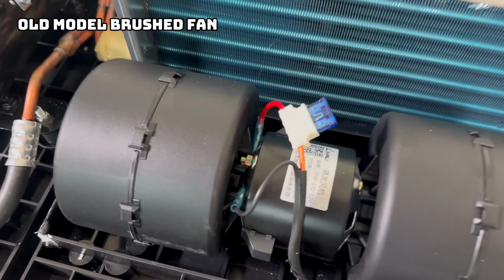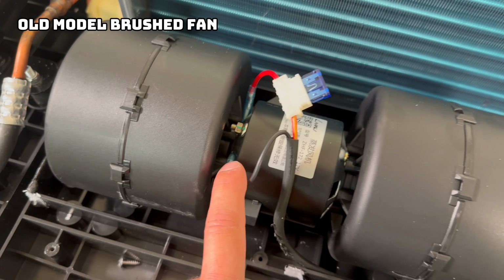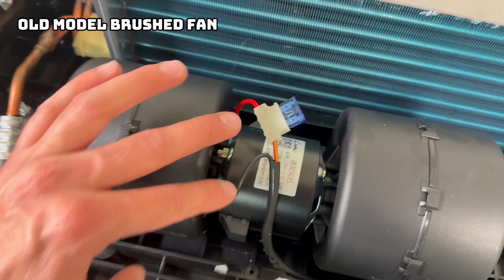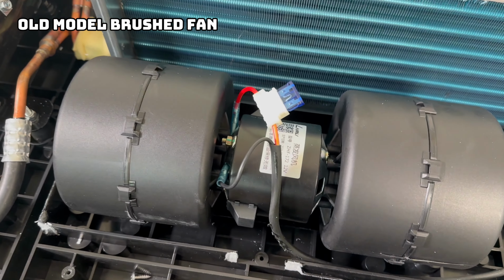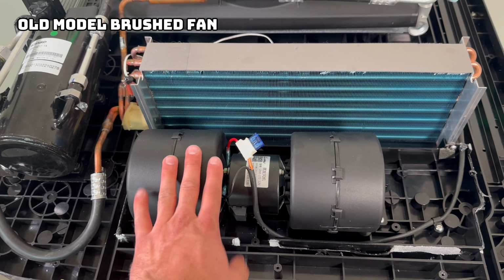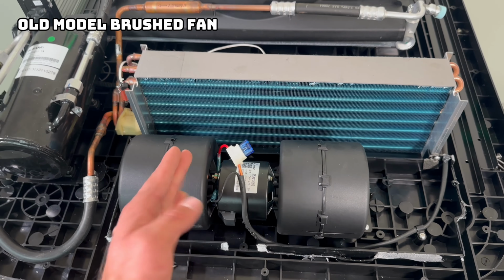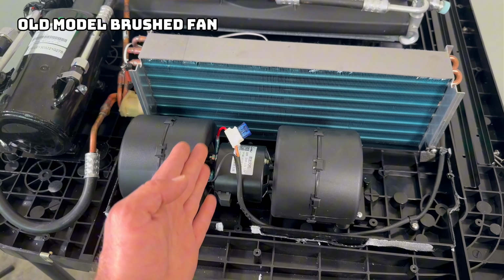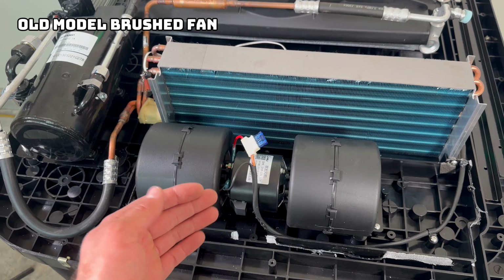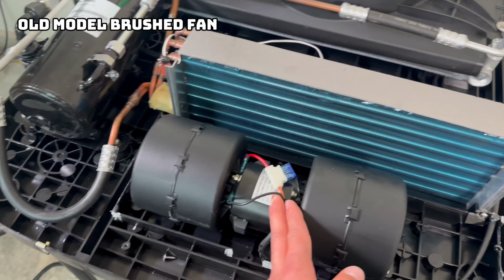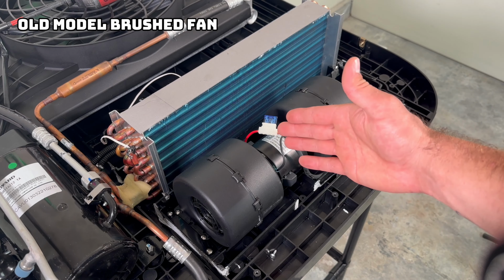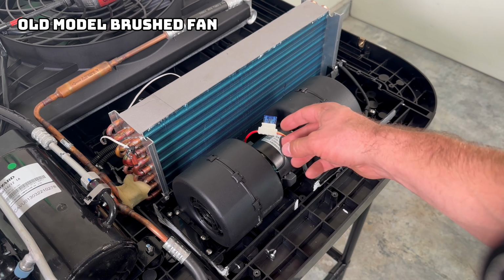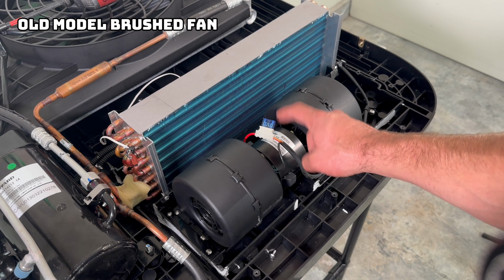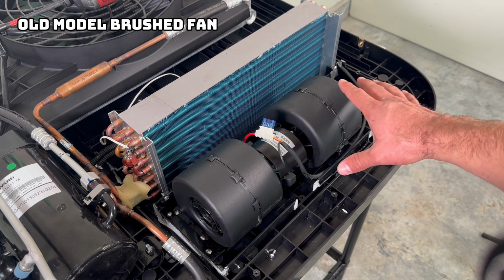On these older fans, the terminals are exposed on the back side. You can take your multimeter, probe these, turn the fan on, and confirm you've got voltage all the way up to the fan. It'll only supply voltage until the EF code is thrown, and once that happens, the voltage is cut off, so check it fairly quickly. If you do find voltage all the way to the fan and it's still not working, it's likely just a bad blower motor, and you'll have to replace the entire assembly.